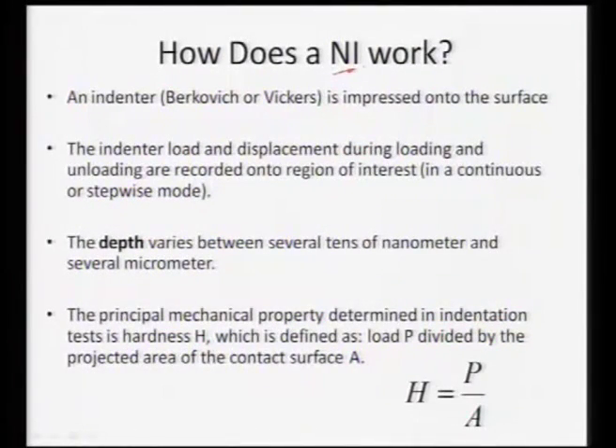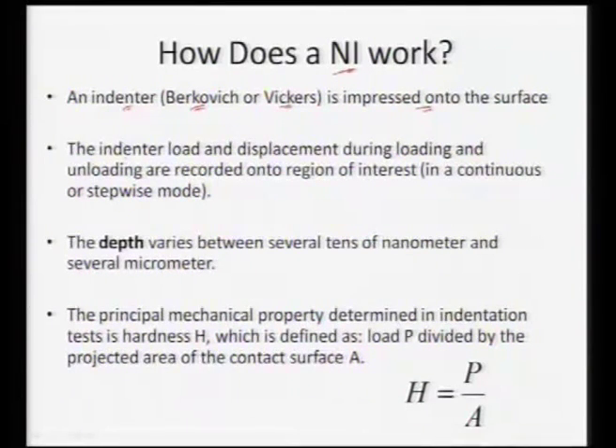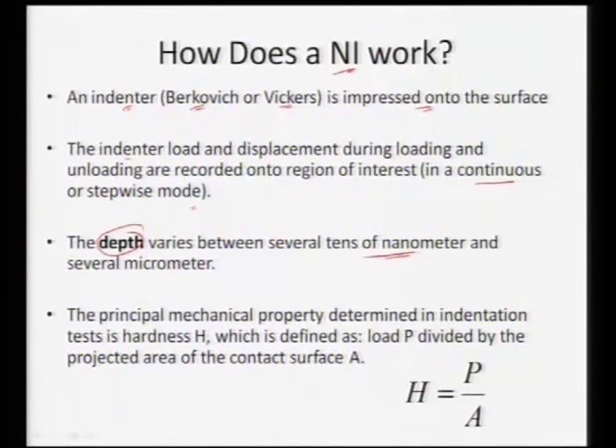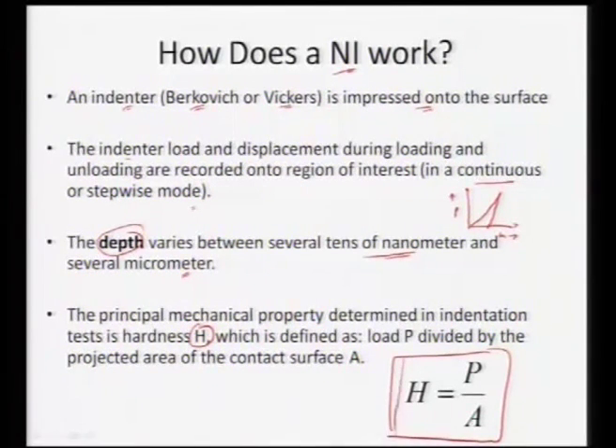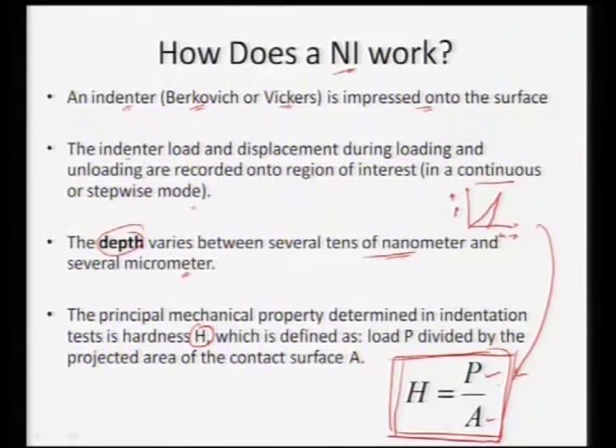How does nano indentation work? We have an indenter — it can have a Berkovich tip, which is a pyramidal tip, a Vickers tip, or a conospherical tip — which is impressed onto the sample surface. The indentation load and displacement are recorded continuously in this instrumented indentation. The depth varies from several nanometers up to micrometers. From the loading and unloading cycle recorded continuously by the instrument, we can measure the hardness, which is given by the load divided by the projected area.